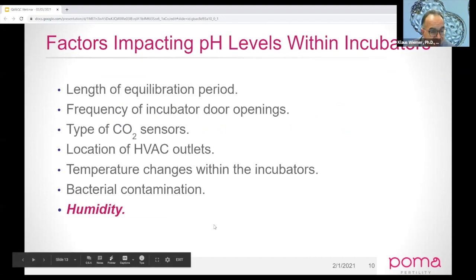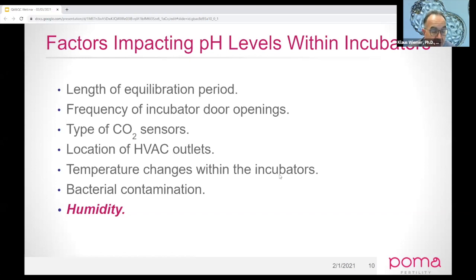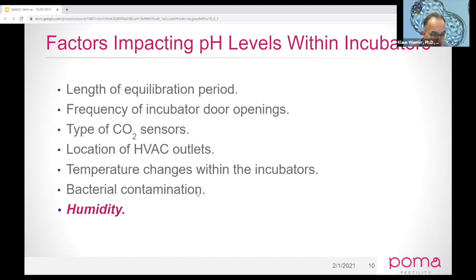What can affect pH levels? We've talked about equilibration and all these factors like CO2 sensors. Obviously the location of your HVAC outlets can impact temperature changes within the incubator itself. Remember, cooler spots are going to be in the lower part of the incubator than upper parts. And obviously if you get bacterial contamination, this is going to impact equilibration of media.